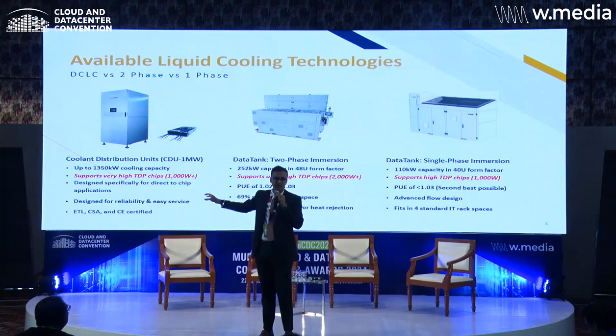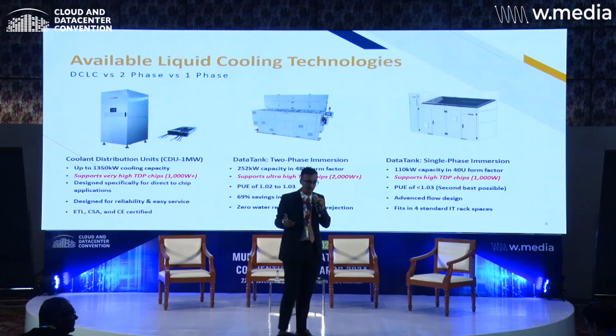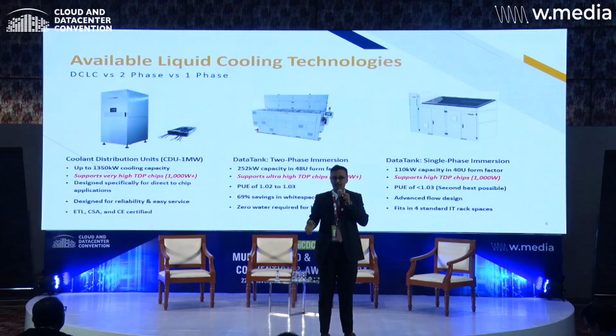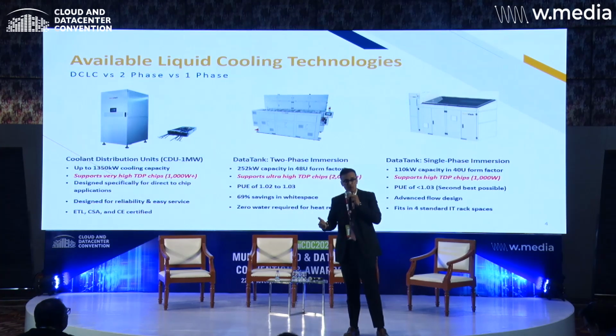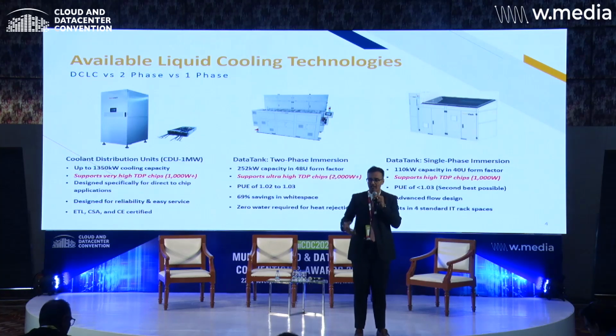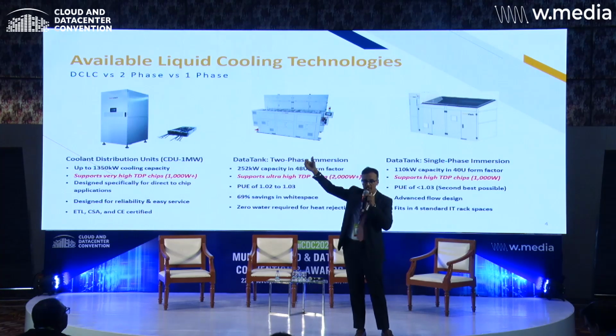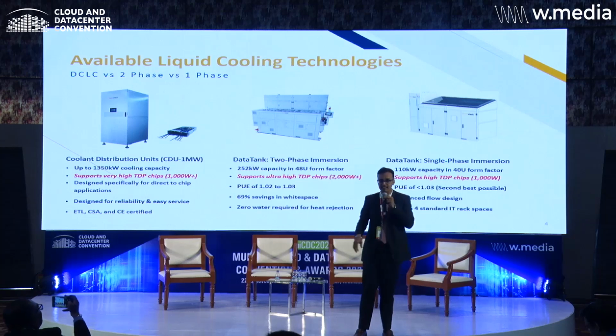So over there, we need to have a CDU unit, which is a coolant distribution unit, which transports the technology coolant system, which might be a 25% polyglycol solution. It lets the chip get cooled through that, and there is a heat transfer which takes place at the heat exchanger. This can take up to 135 kilowatts per rack, which is a very good compute capacity in today's world because the AI loads that are coming and are defined are up to 100 kilowatts. So direct to chip is a very efficient system which can be added to your existing data center as well. Take a CDU, connect your chiller and put it into the CDU and start transferring the TCS.